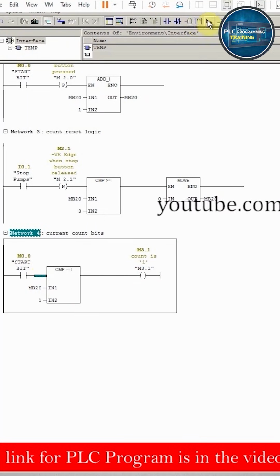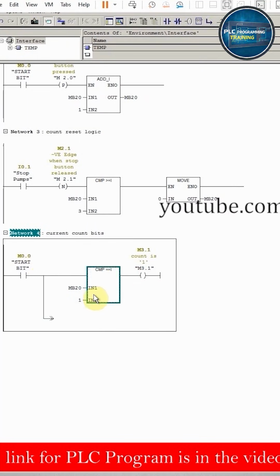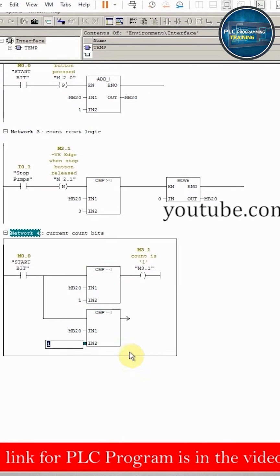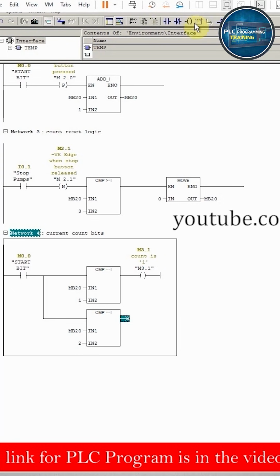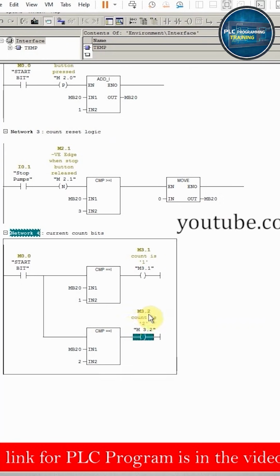Next we will insert a branch here and we will use the same comparison operation and compare it with the 2. Now, whenever the value in the MB20 is equal to 2, we will activate a coil here which is M3.2. Now this will indicate that we have pressed the start push button 2 times.